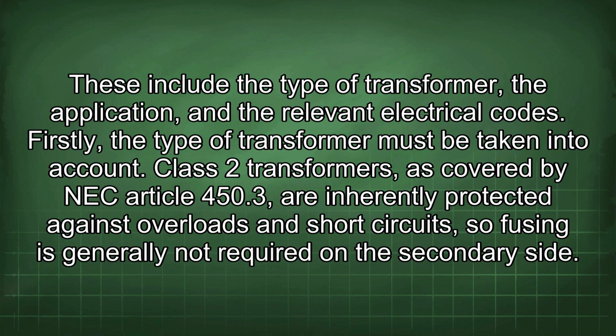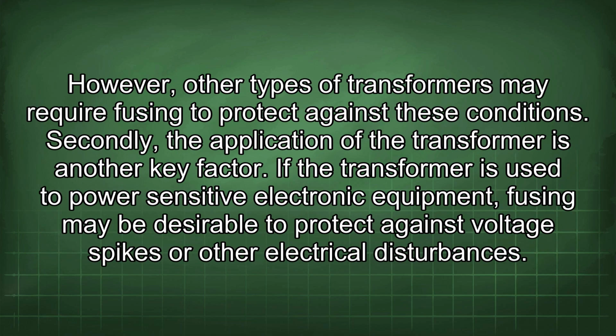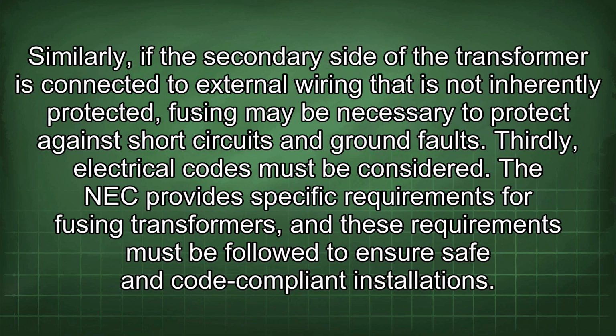Firstly, the type of transformer must be taken into account. Class 2 transformers, as covered by NEC Article 450.3, are inherently protected against overloads and short circuits, so fusing is generally not required on the secondary side. However, other types of transformers may require fusing to protect against these conditions. Secondly, the application of the transformer is another key factor. If the transformer is used to power sensitive electronic equipment, fusing may be desirable to protect against voltage spikes or other electrical disturbances. Similarly, if the secondary side of the transformer is connected to external wiring that is not inherently protected, fusing may be necessary to protect against short circuits and ground faults.